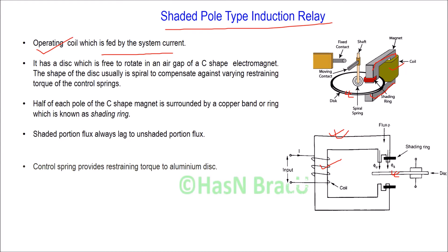This disc is normally made of aluminum so as to have low inertia, and therefore due to having low inertia it needs less deflecting torque for its movement. The shape of this disc is usually spiral, as it can compensate against varying restraining torque of the control spring. Since the shape of disc is not perfectly circular, a suitable balance weight is provided on the part of the disc which has a smaller area.